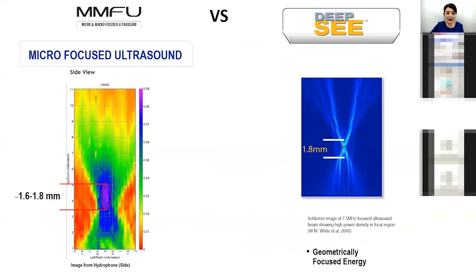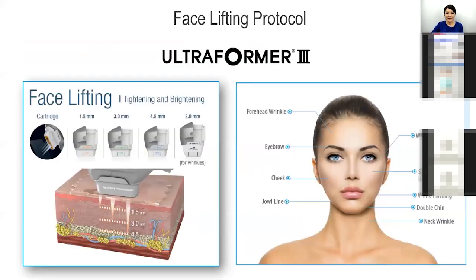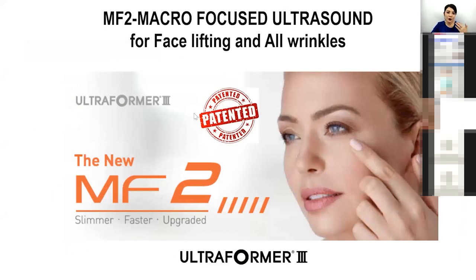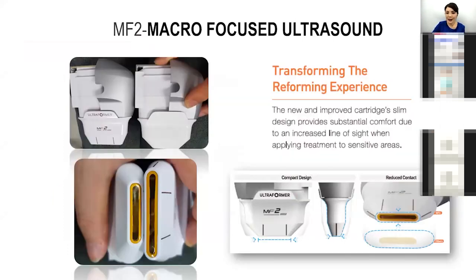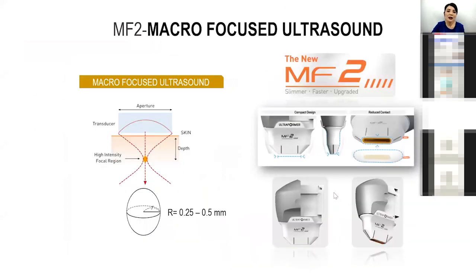So this is the differentiation from the Ultraformer. And again, when comparing the micro focus ultrasound mode of Ultraformer and Ulthera, I think it's pretty much the same size. And you can see this is 1.8 mm in shape when you are looking at it two-dimensionally. This is when we're talking about face. So, as I told you earlier, this is micro focus ultrasound and 2 mm is macro focus ultrasound. That is why we just recently got the new upgrade with the compact design. It's easy to use and the dot is bigger, which means you treat the skin in a larger area compared to micro focus.